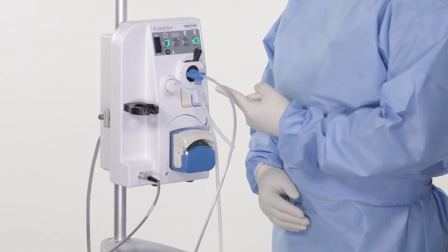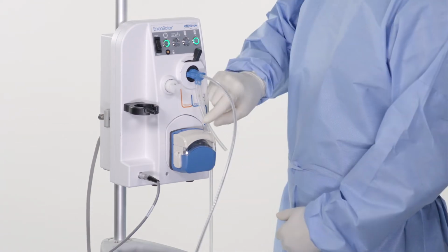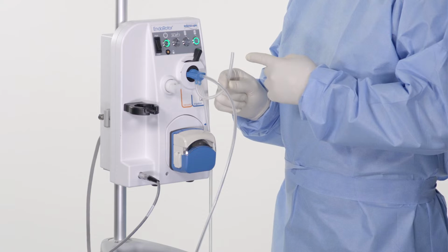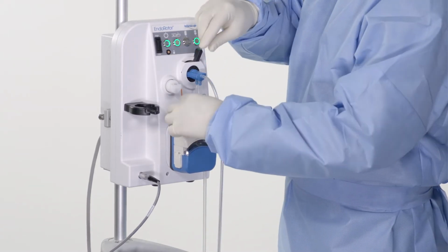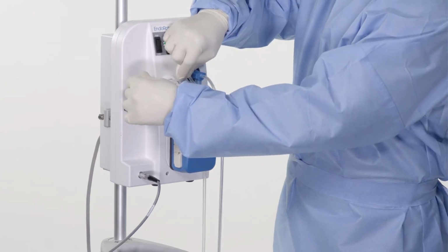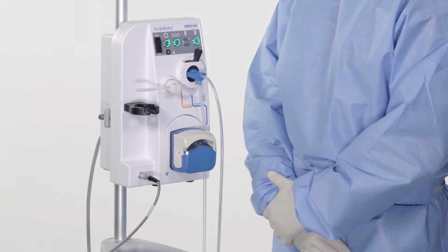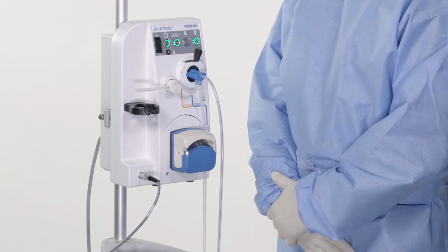On the bottom surface of the proximal housing are two connected tubing sets. The shorter of the two tubes is the specimen trap connection vacuum tube. To load, press the vacuum release button. Stretch the tube and place into the vacuum release valve until seated. Take care when stretching the tubing to ensure your right hand does not hit the catheter housing with force. Hitting the housing with force may damage the catheter.